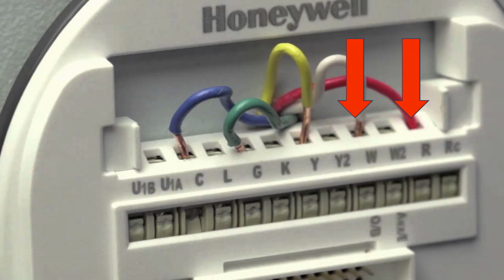Same thing with the R and W on a thermostat. With the thermostat not calling for heat, the switch is open, and so you will read 24 volts. When the switch closes and the thermostat calls for heat, your 24 volts will go away and you will not read 24 volts across R and W. Another way you can check the stat is by checking between common and W, and this works exactly the opposite. If the thermostat is calling for heat, you will have 24 volts between common and W, and if the thermostat is not calling for heat, you will not have 24 volts across common and W. The R to W method is most commonly used as some thermostats do not have a common terminal.